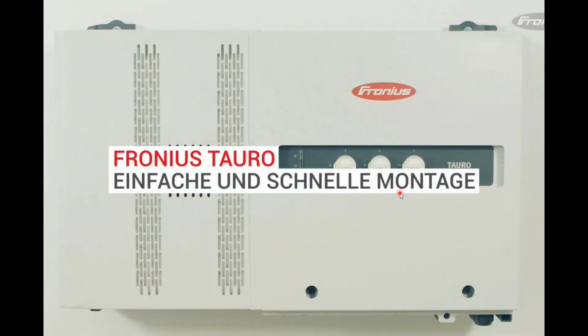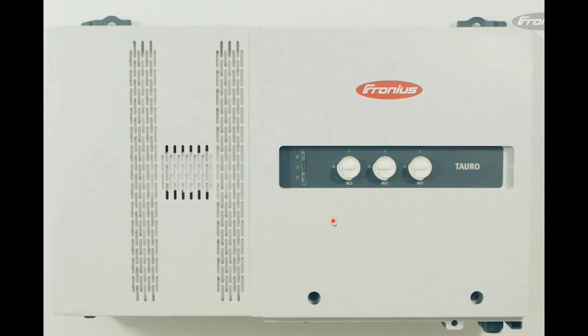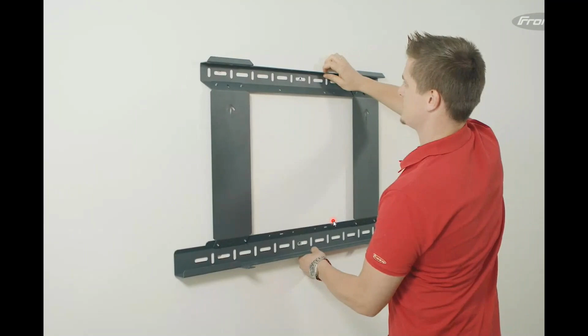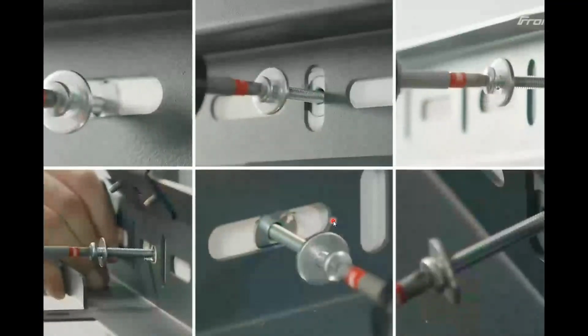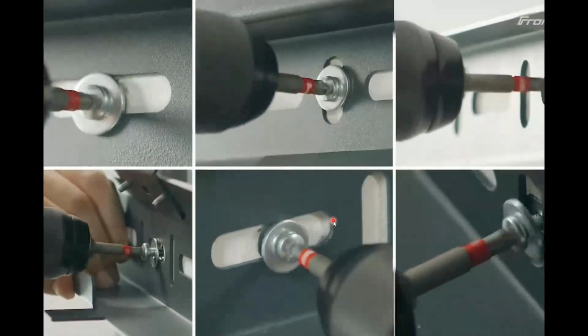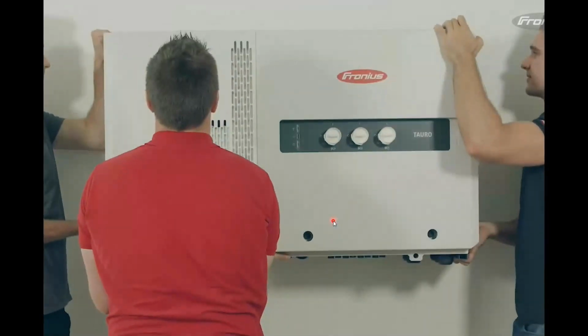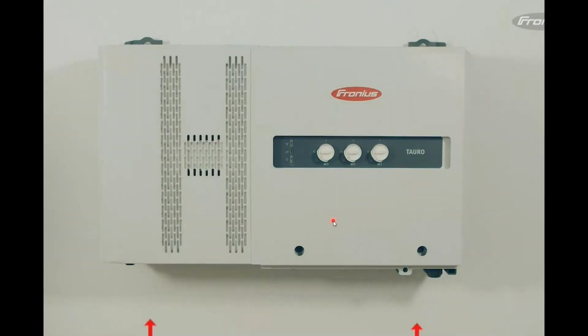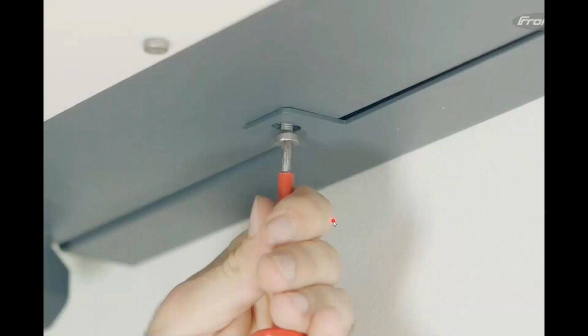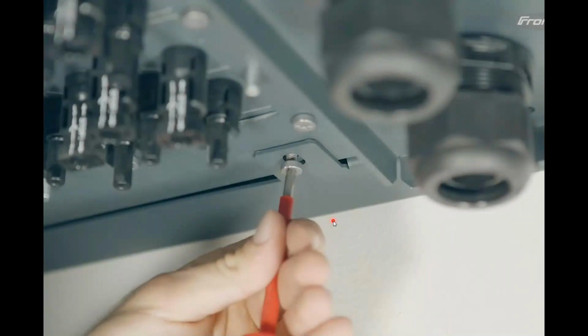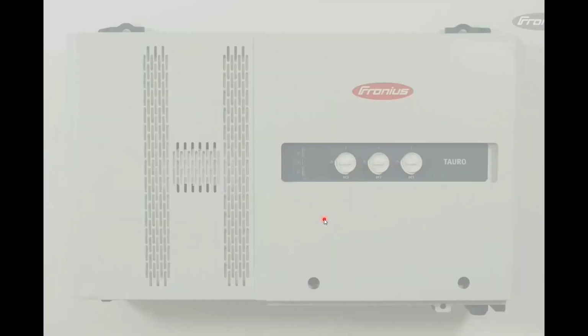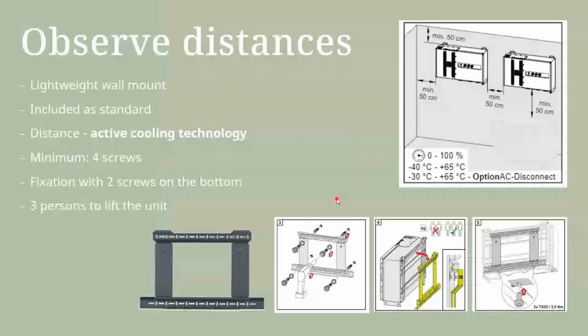So this is a summary of how the inverter can be mounted. Ensure your fixtures are ready in the right position, then have the wall mount rack installed and screwed properly, and then install the inverter. Mind the weight, so have as many people as possible helping, though basically three people is okay. Ensure you have the screws to hold down the inverter underneath. Once that's done, you're ready to continue to the next step, the wiring.